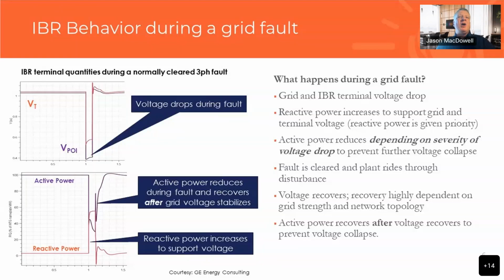I think harmonizing that language with the other standards is good, because the challenge with calling out the active power and reactive power performance is that under normal conditions, that I'm showing here on the left, when there's a voltage disturbance, when there's an electrical fault, and when the voltage is reduced, it's a very important and good behavior for the grid, and a necessary behavior for the grid, for that active power to be reduced during the fault. And the reason is we want to make sure that we don't push too much active power across the network into a voltage that's already depressed, into a voltage that's not healthy. Otherwise, we're going to further collapse the voltage. We're going to further cause reliability risk, and could also cause more cascading outages.